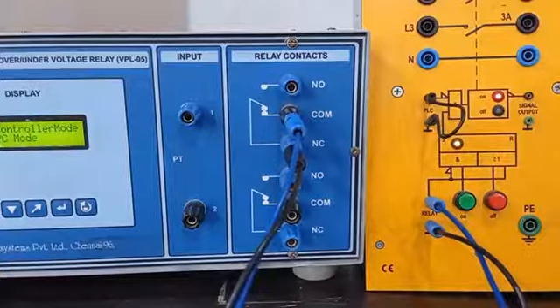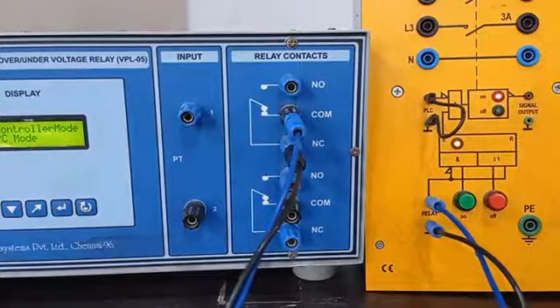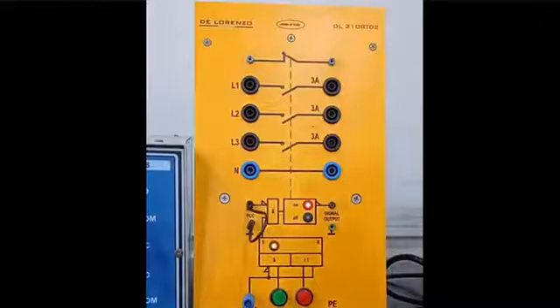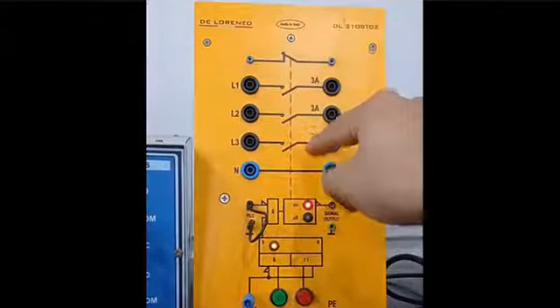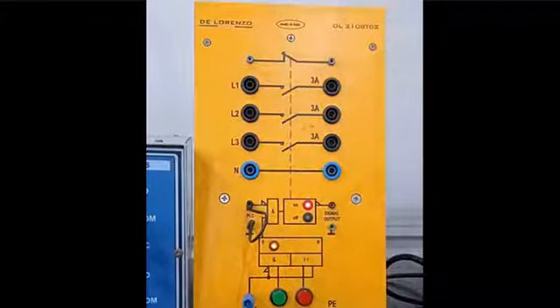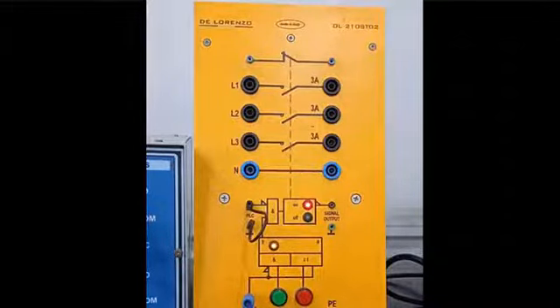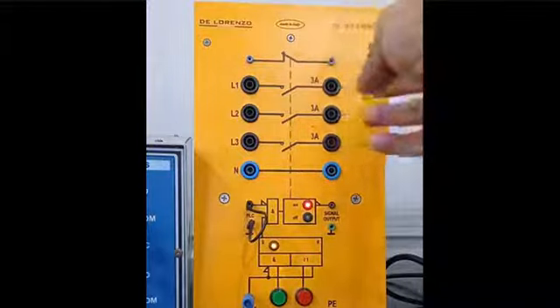You are going to connect all the circuit breakers with some appropriate relay in order to control those circuit breakers with the relay. On tripping of the relay, the circuit breaker contacts will become open. There is one more instruction to use the circuit breaker. As you can see, the rated current of this circuit breaker is three amperes, meaning its contacts are designed to interrupt a maximum of three amperes. But in many experiments, fault current can be as high as six or seven amperes. So in order to protect the circuit breaker against that fault, and since the majority of those experiments which require current above three amperes are single-phase experiments, we connect these three contacts in parallel with each other.